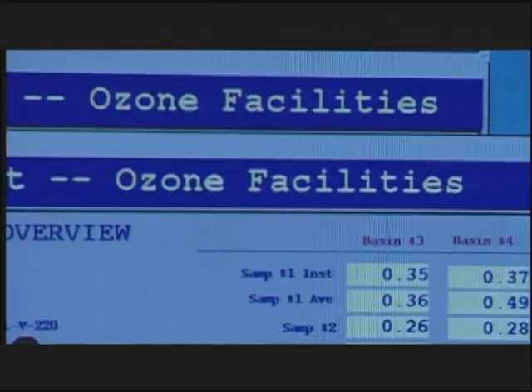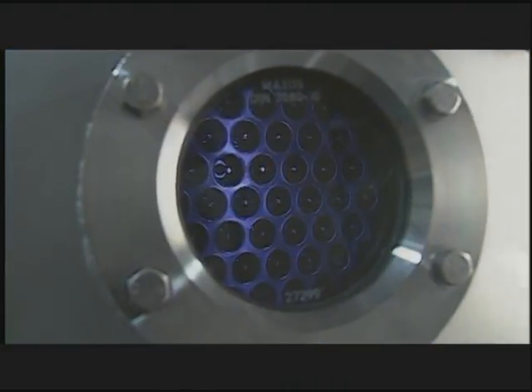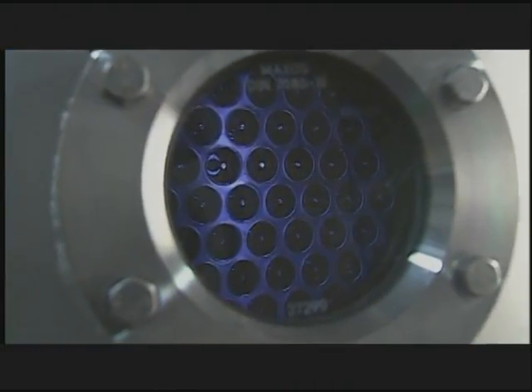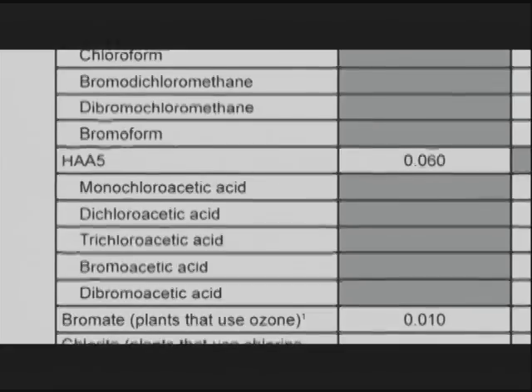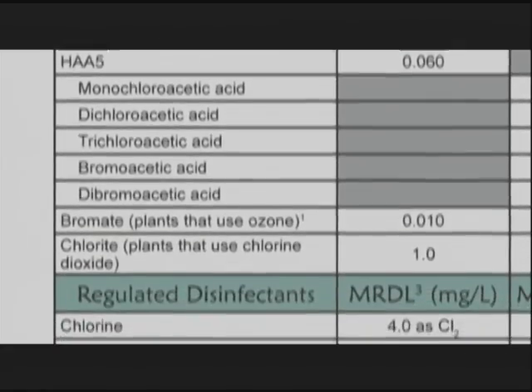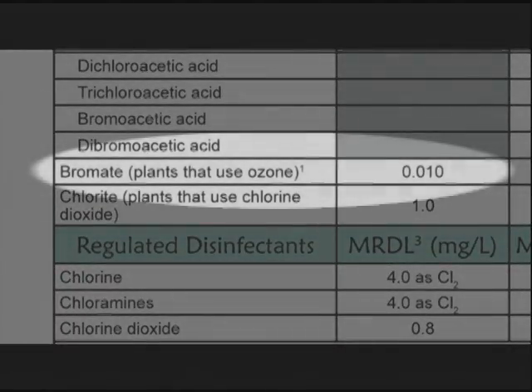Plants that use ozone as a disinfectant have to be concerned with the formation of bromate, which occurs when bromide in the source water reacts with ozone. The maximum contaminant level for bromate is 0.01 milligrams per liter, or 10 parts per billion.